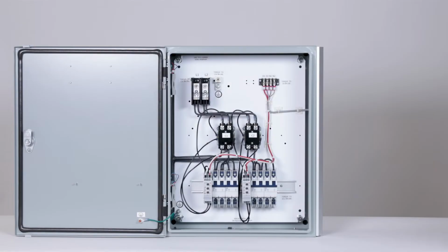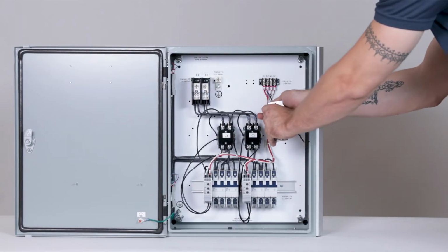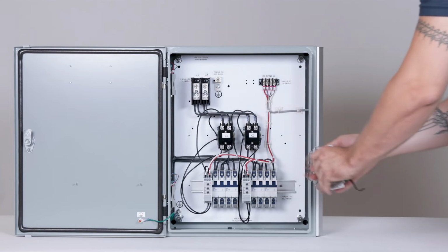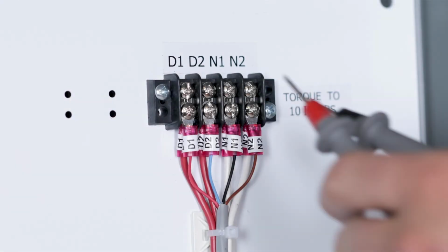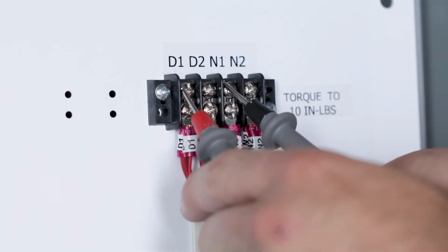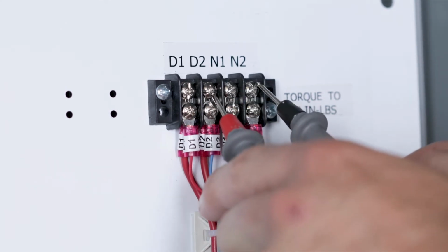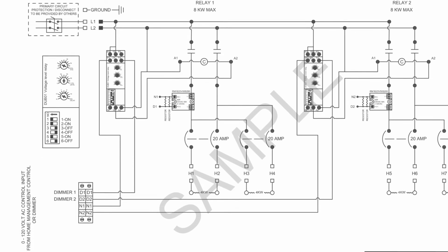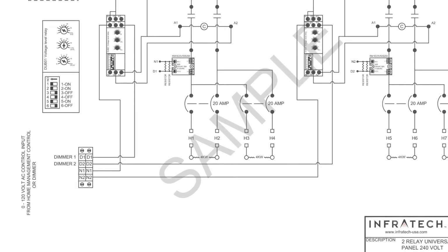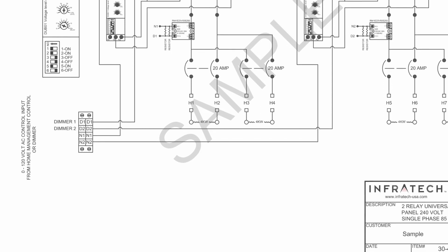Once the 0 to 120 volt AC dimmer is wired properly, connect the 0 to 120 volt AC control signal to the control terminal strip in the upper right hand corner of the control panel, for example D1, N1, etc. Your custom control configuration will determine exactly where to land. You can refer to your wiring diagram for guidance.